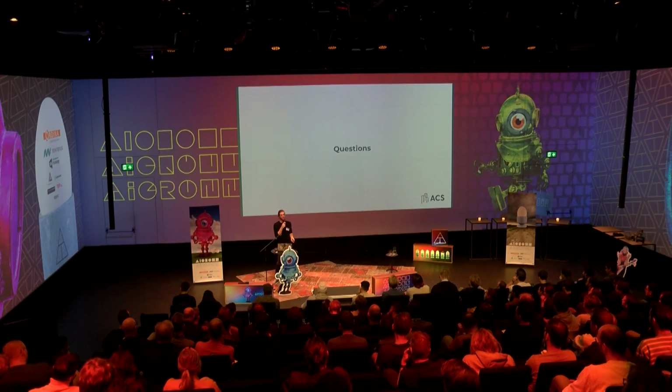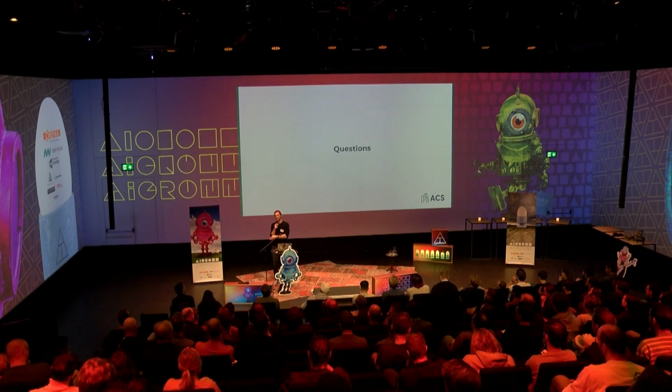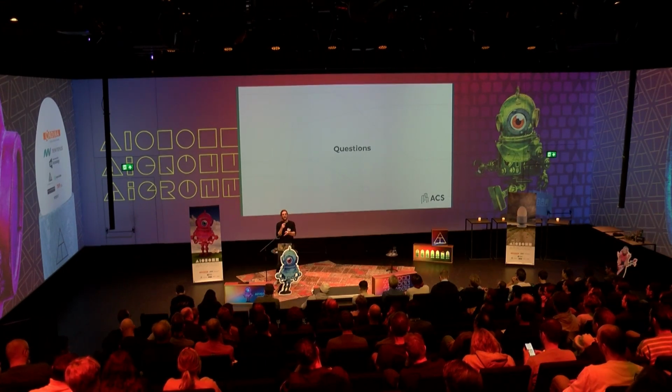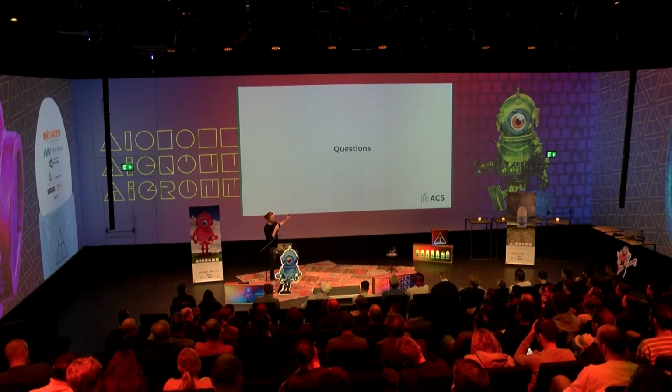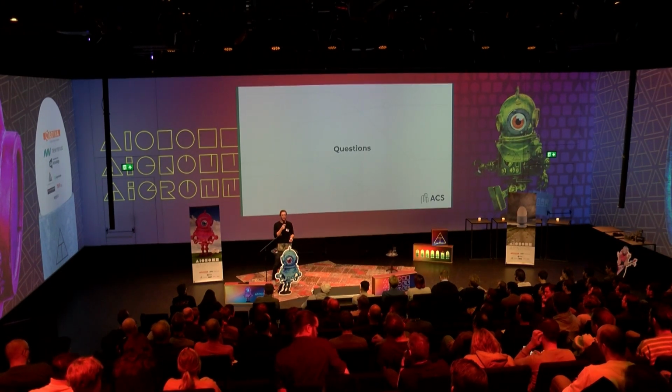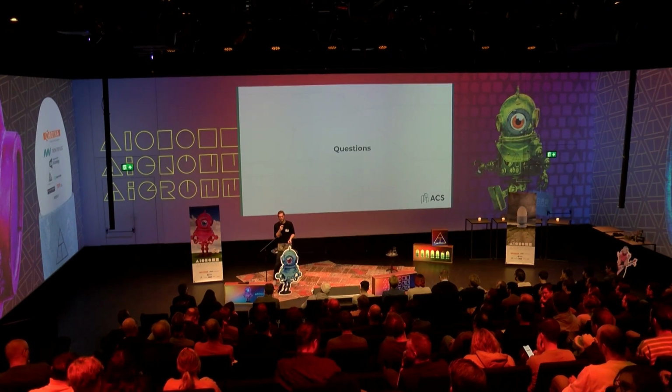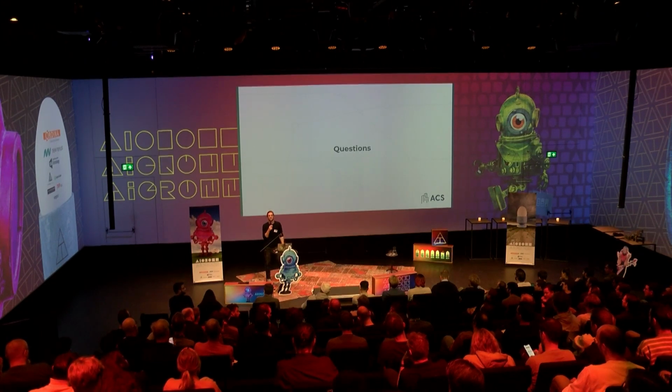But I found that reinforcement learning doesn't work really well in our industry. Why? Because our actions and responses, so the rewards that you get after taking action, are very delayed. You take an action and then half an hour later you see the result in the room temperature, which means you need a lot of data, like 20 years of data of a building to really get a good model. And furthermore, every building is different, so you can't really generalize across buildings. You have to make specific models for specific equipment, and that just doesn't work that well. So that's why we use supervised learning. Okay, thank you.